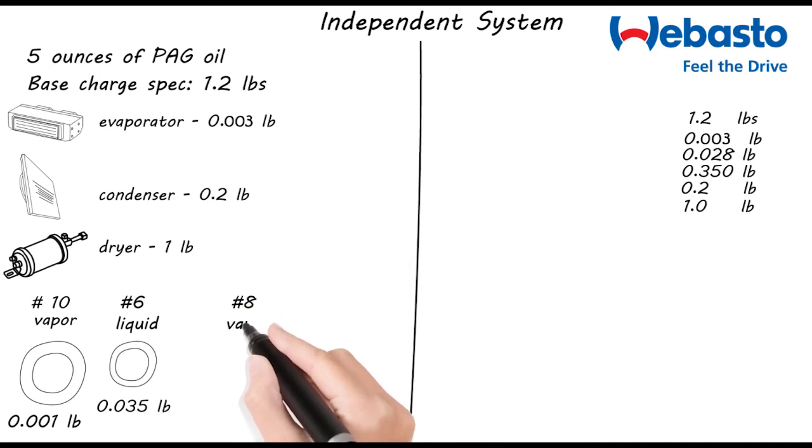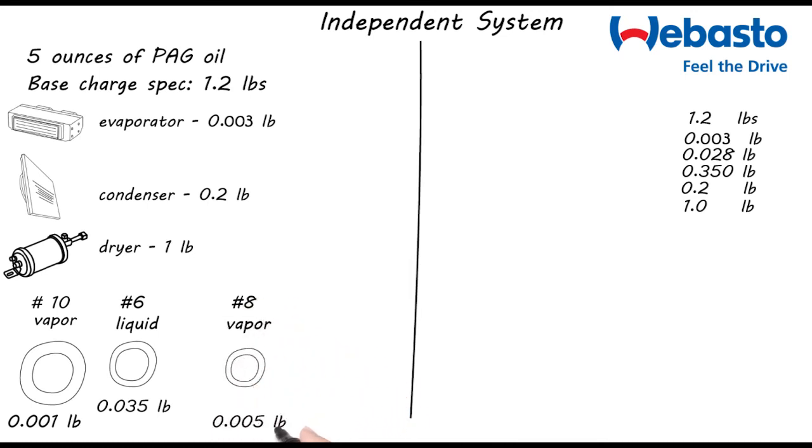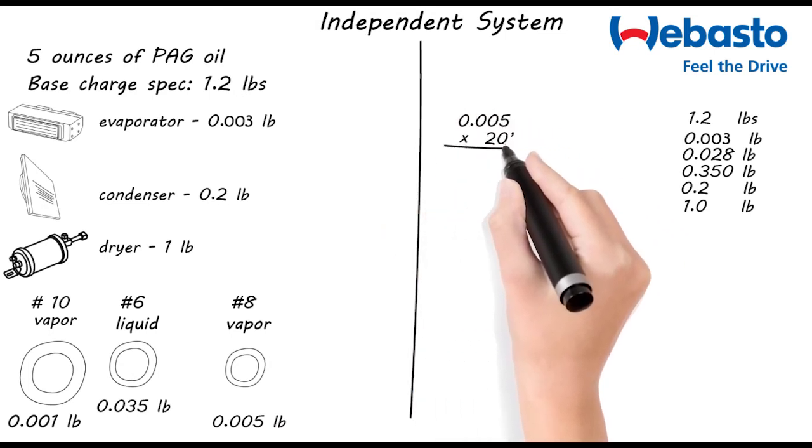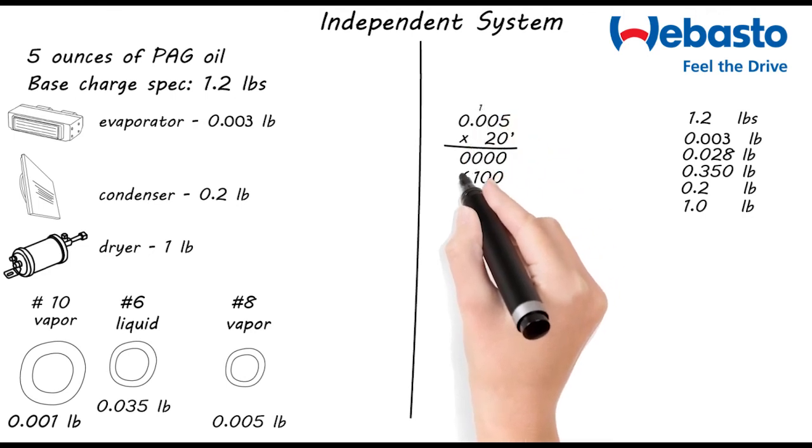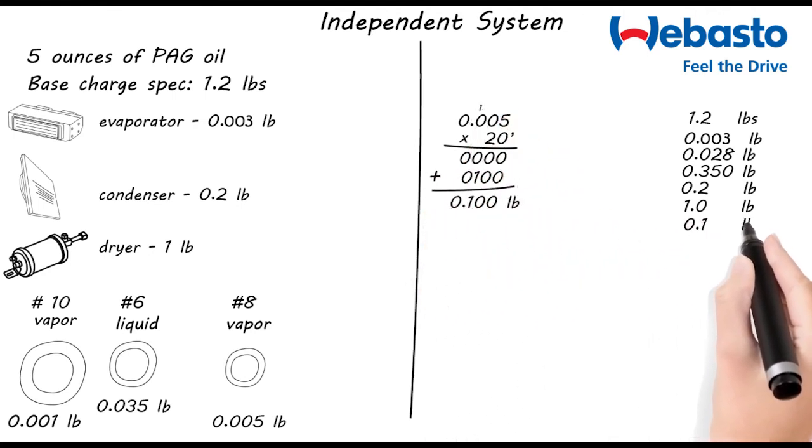Just like last time, we'll have to figure out our refrigerant quantities based on the length of the hose we've installed. We'll add 0.005 pounds of refrigerant per foot of number 8 line on the vapor side. In this example, we installed 20 feet. So the math works out to 0.1 pounds of refrigerant.